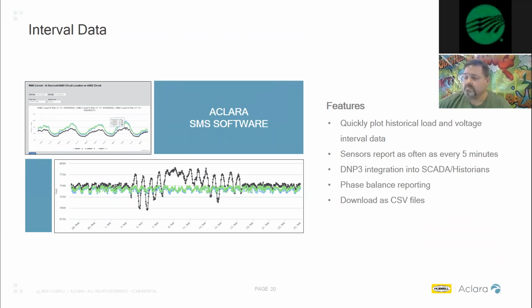Depending on the type of sensor deployed, key measurements include load current, voltage, and all the power measurements—watts, VARs, VAs, fault currents, power factor, phase angles, sags and surges. Another is conductor temperature, giving you an ambient conductor temperature of the conductor itself, and also some voltage harmonics with the power sensor.